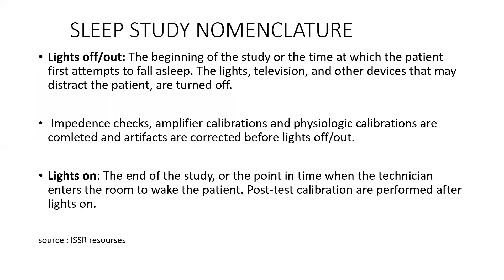Let us begin with the nomenclature used in a sleep study report. The first is 'lights off' or 'lights out' — the beginning of the study or the time at which the patient first attempts to fall asleep, when lights, television, and other devices are turned off. Impedance checks, amplifier calibrations, and physiological calibrations are completed before the lights-out time, and artifacts are corrected. 'Lights on' is the end of the study when the technician enters the room to wake the patient; post-test calibrations are performed after lights on.